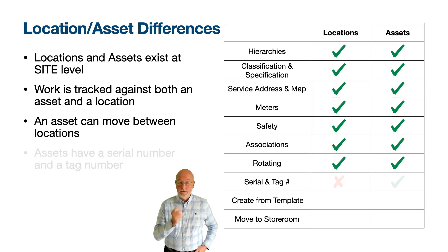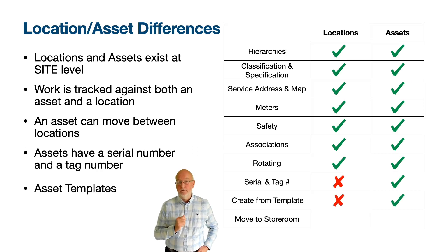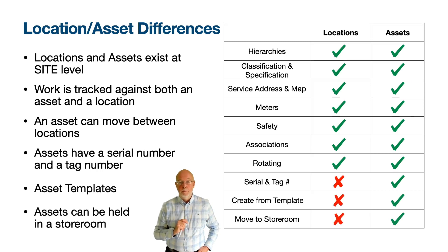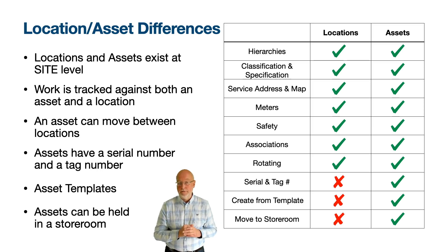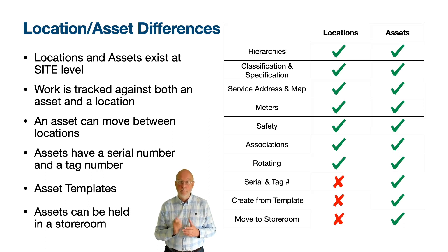In Maximo, assets have a serial number and a tag number and can be used for recording downtime — locations cannot. Assets can be generated or updated from an asset template, and they can be moved into a storeroom where there will be an inventory balance. When it is time for an asset to be repaired, assets at an operating location can be swapped with a store of assets. An asset can also be moved to a different site — and if the asset physically moves, like a boat sailing between islands, it can be repaired at a port on another island. In Maximo terminology, this is a repair location.